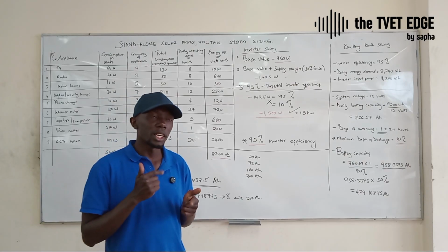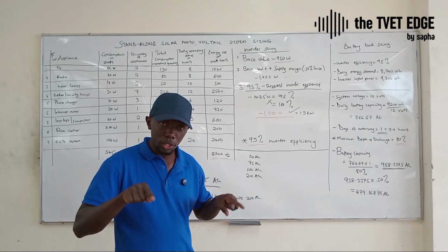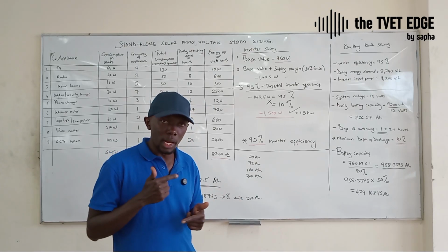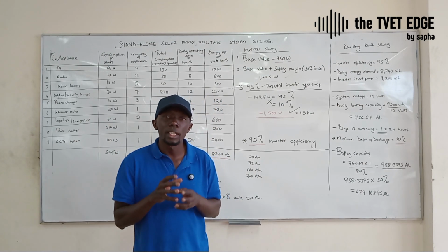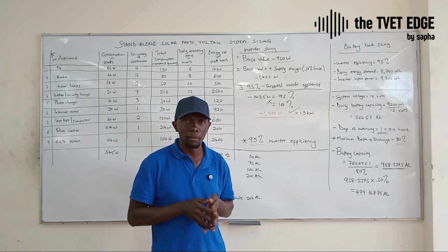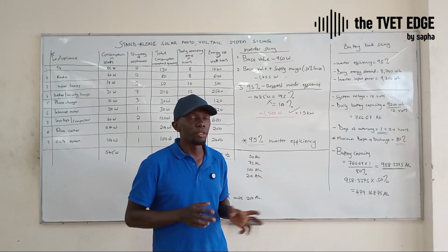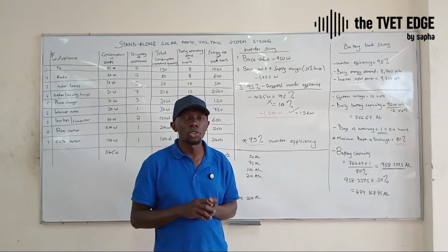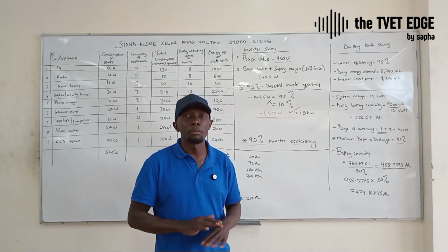The process of charging and discharging involves some chemical reaction within the battery unit itself. A continuous charging cycle ensures that these chemical reactions degrade your battery faster than expected. If your battery is constantly charging and discharging, if it was meant to serve you for, let's say, 4,000 charge cycles, it might not be capable of going past 3,500 while delivering optimally.